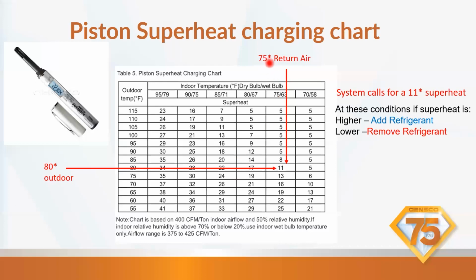So if you have a 75-degree return air, you're going to use this column. If you have an 80-degree outdoor, we're just going to track over to 11 degrees superheat. We want that superheated vapor to be 11 degrees above saturation. So the system calls for 11 degrees superheat. If you have a 16-degree superheat, you're going to add refrigerant to lower that superheat.